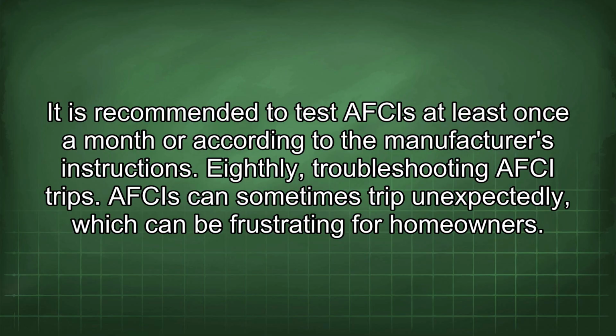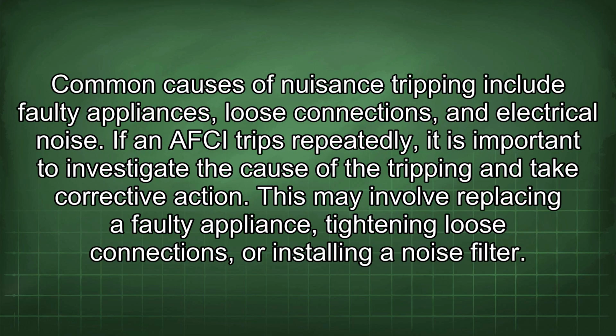Eighthly, troubleshooting AFCI trips. AFCIs can sometimes trip unexpectedly, which can be frustrating for homeowners. Common causes of nuisance tripping include faulty appliances, loose connections, and electrical noise. If an AFCI trips repeatedly, it is important to investigate the cause of the tripping and take corrective action. This may involve replacing a faulty appliance, tightening loose connections, or installing a noise filter.